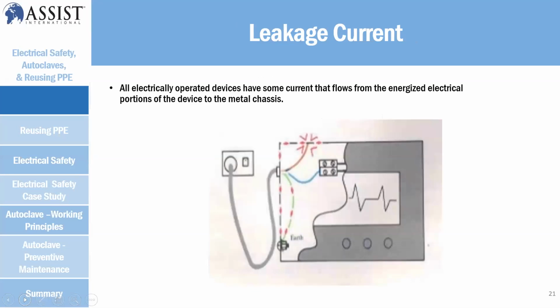So, leakage current on the equipment: what happens is, with a metal chassis, a body with metal casing, when there's a leakage, for example a live wire broken from the main line touches the metal chassis, when someone touches it, you're going to get electrocuted. Like, for example, an autoclave. Most big autoclave units have a metal case and should be grounded, but one of the wires may touch the body of the chassis or something like that. Eventually, with the earth, it's going to trip if you've got a proper fuse and circuit breaker. But if you don't have any other safety precaution, someone is going to get hurt.